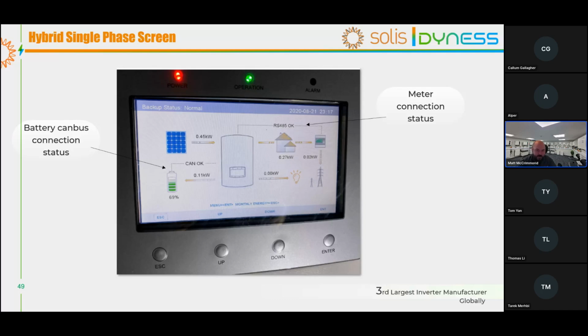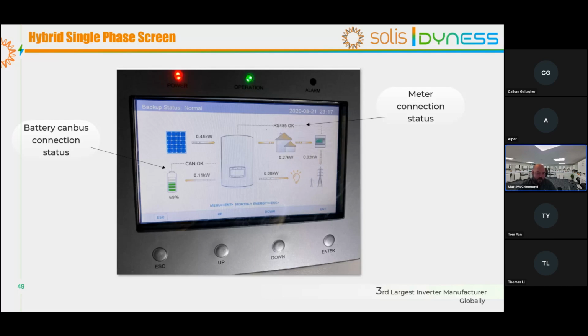So first is the load. Does that value look accurate? For example, if you turn on the kettle and it went up to 2-3 kilowatts, then I would suspect yes. If you switched it on and it went up to 10 kilowatts, then I would suggest that maybe the readings are wrong. If, for example, you see zero load there and the export is high, then that may be an indicator that the CTs are around the wrong way. So, for example, there's no PV production, there's no power coming out of the inverter, but the CT is reading export, then that would be an indicator that the CT is around the wrong way.